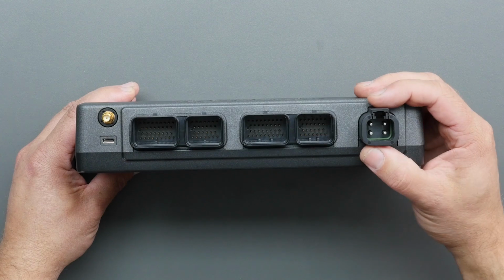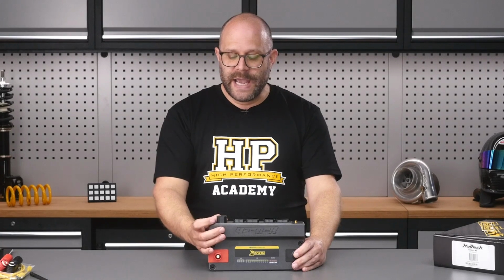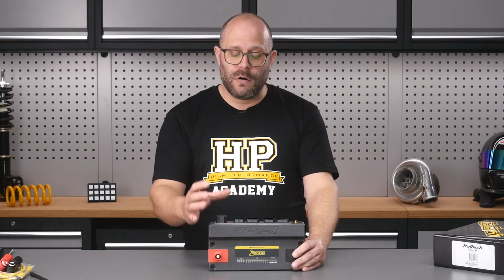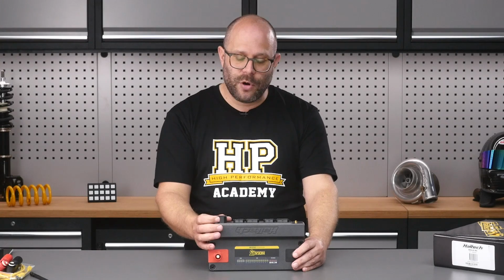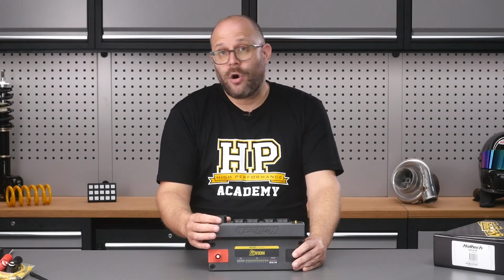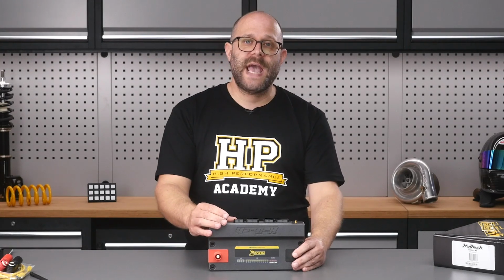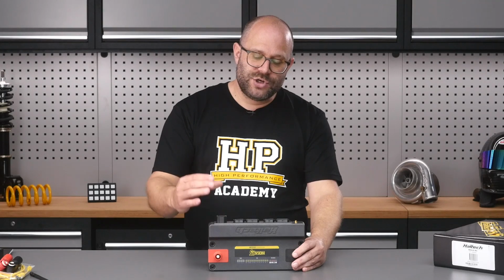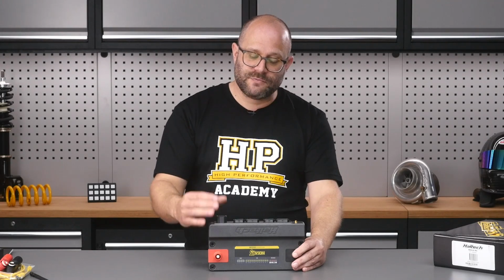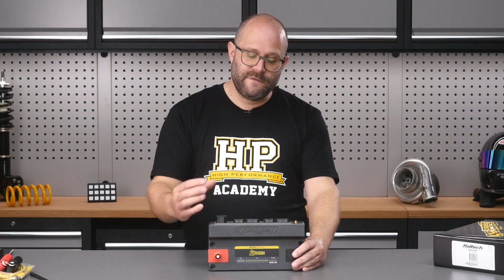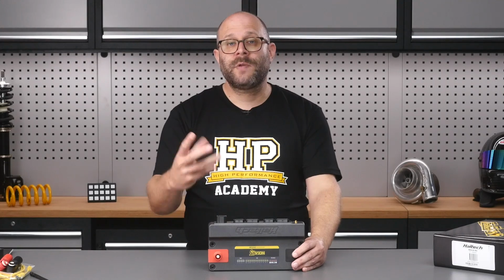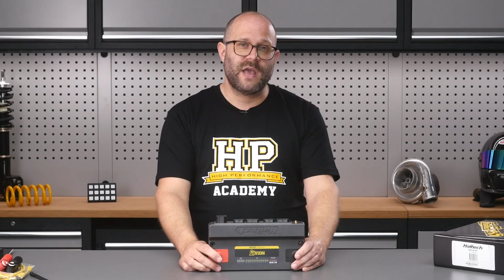You can see there we've got some pretty chunky pins in there. That's because this is a high current output port. Each one of those pins is capable of 25 amps output, so you've obviously got to have the corresponding wire size going into that to handle that current, which interfaces really nicely with the DTP 4-pin connector that would go in here. Comes with terminals that are obviously the right size to crimp onto that heavier gauge wire.